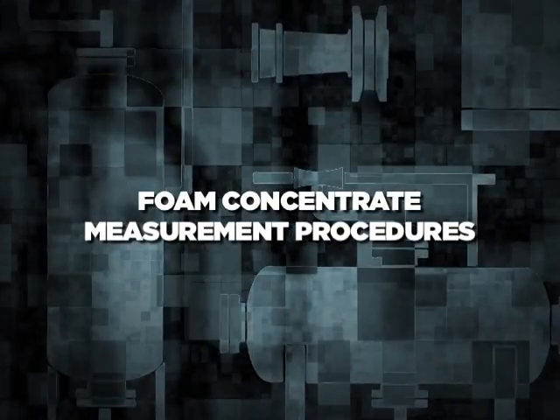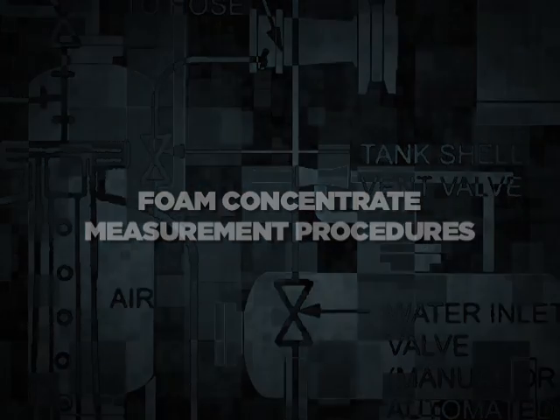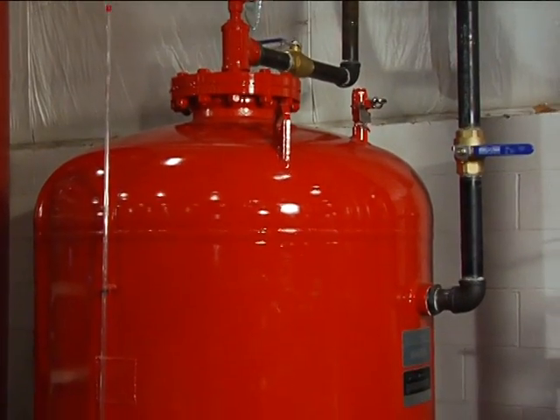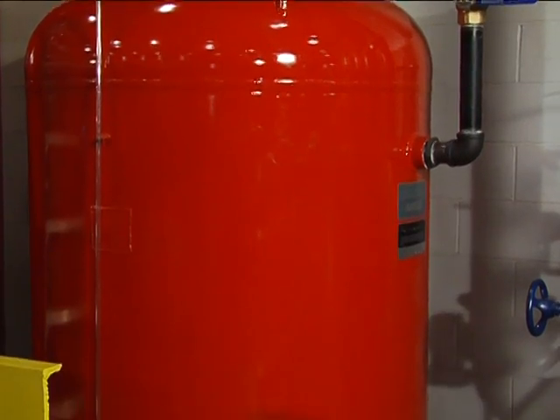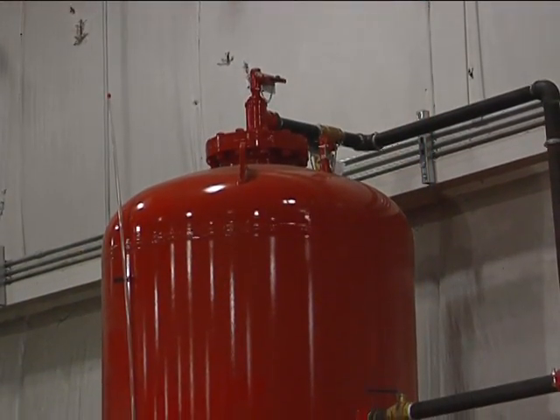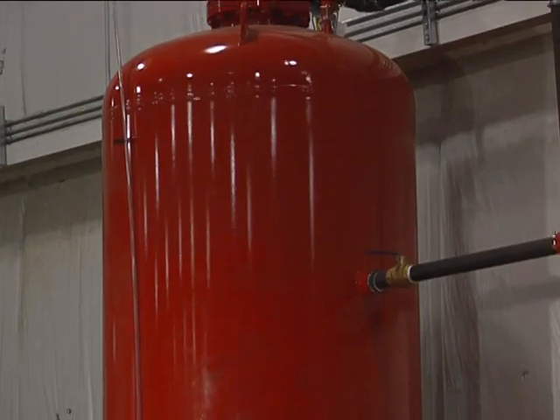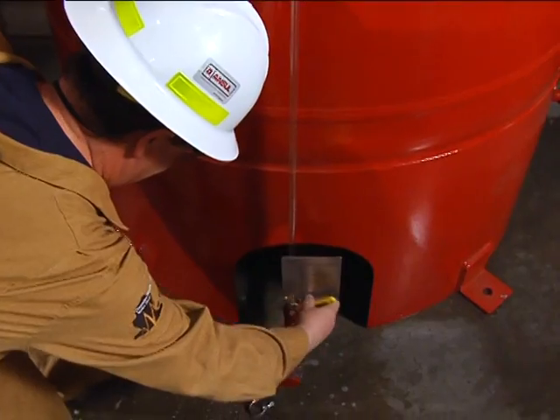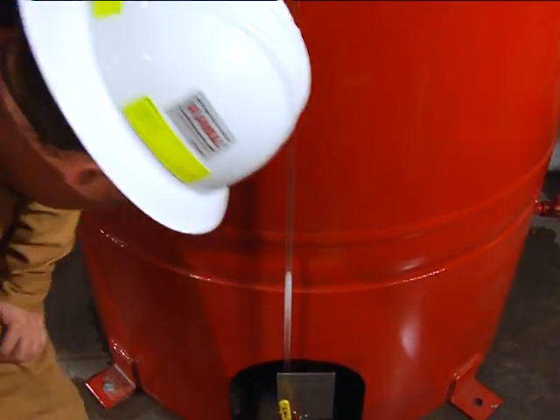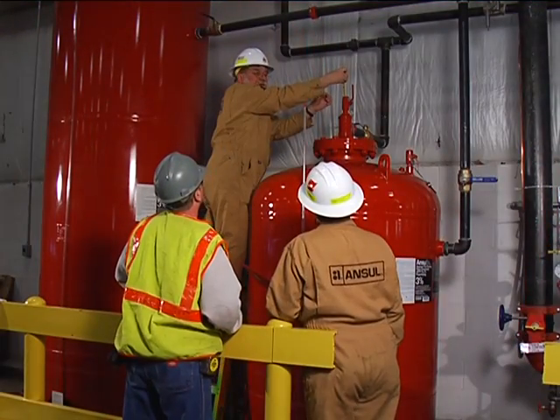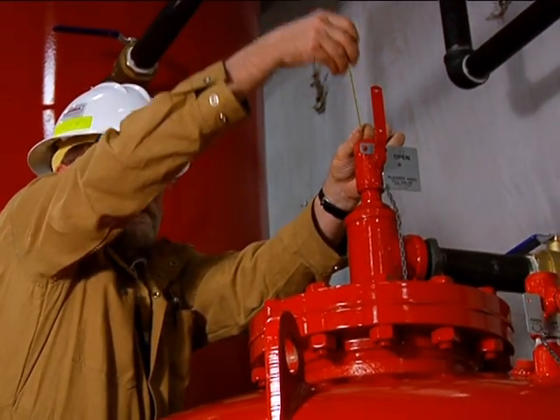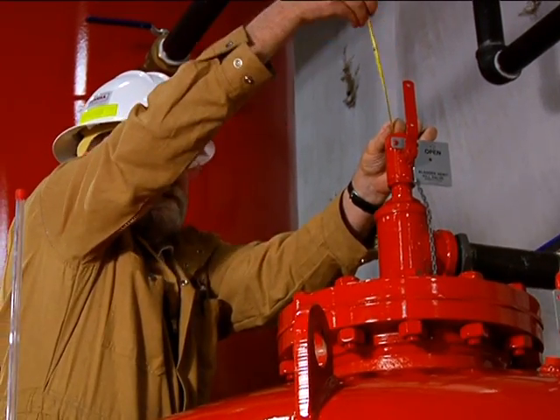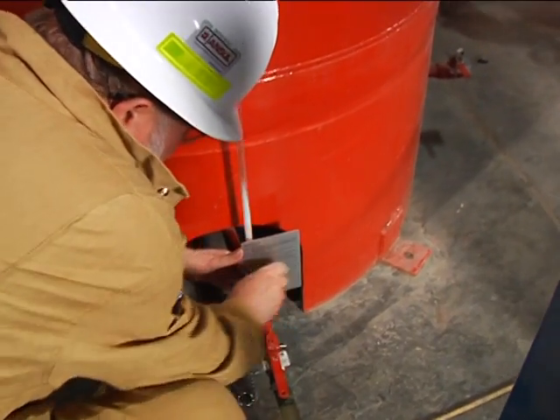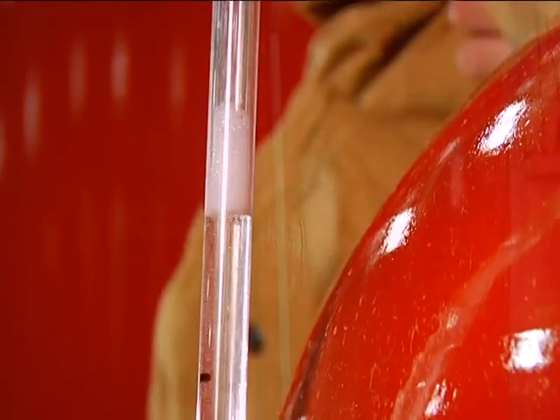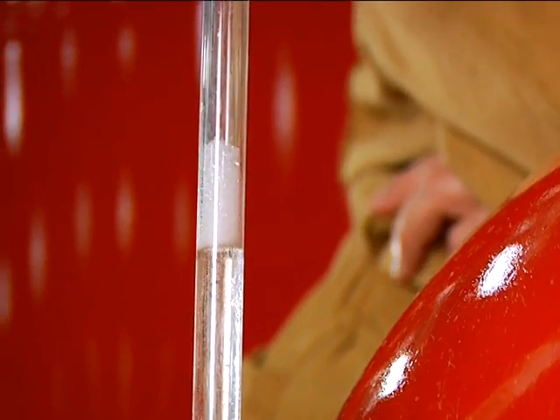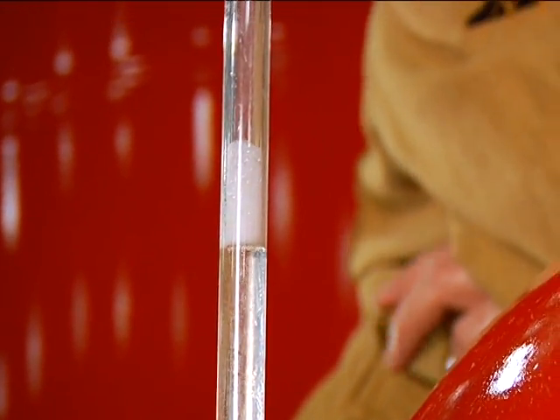Foam concentrate measurement procedures. Depending on the Ansul equipment provided, 2 methods are acceptable for estimating the foam concentrate within your Ansul bladder tank. One is using the sight gauge. The other is using a dipstick or line. Both methods are appropriate for either horizontal or vertical bladder tanks, but keep in mind neither method is exact. Instead, both methods of measurement will provide a close estimate of the bladder contents.